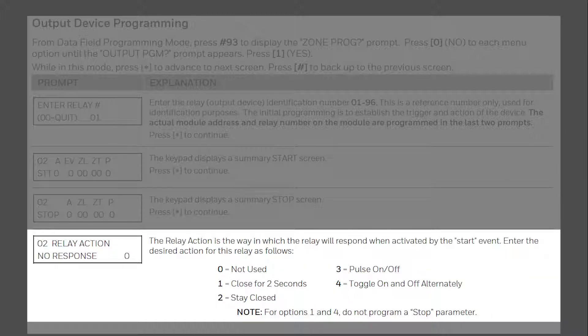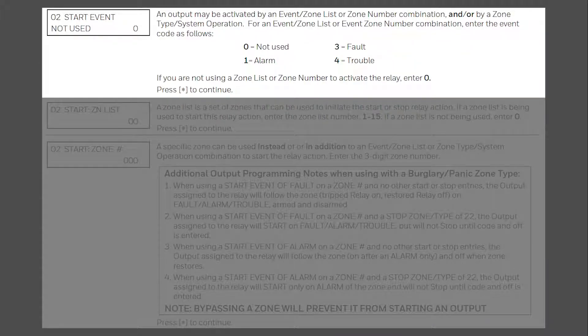Next, choose the action of the relay. The most common will be a 1 for close for 2 seconds and a 2 for stay closed. Keep in mind that if your relay is wired normally closed and common, this stay closed action will still change state of the relay and switch from the normally closed state to an open state. Press star. The start event will only be used if the relay will be activating on a specific zone number or a zone list. The available events are alarm, fault, or trouble. If you are using a zone type to activate the relay, press star to skip this prompt.